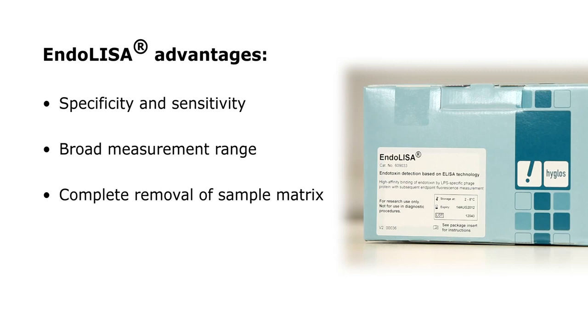EndoLISA overcomes the limitations of homogeneous assay methods. It provides excellent endotoxin specificity and sensitivity without dilution of samples, detection of endotoxin concentrations ranging from 0.05 to 500 EU per milliliter, a heterogeneous assay format that enables the complete removal of sample matrix and ensures accurate results, an end point fluorescence assay correlating to all quantitative LAL methods, and a solution free of animal products that provides relief for dwindling horseshoe crab populations.